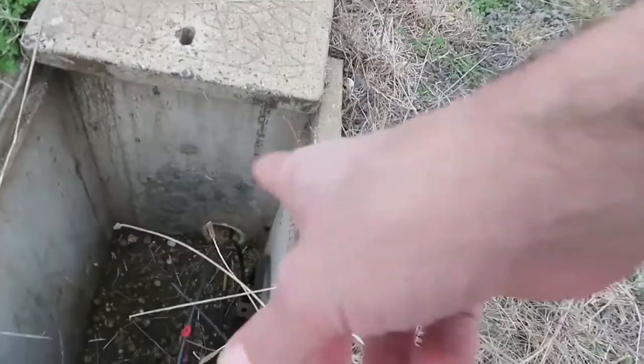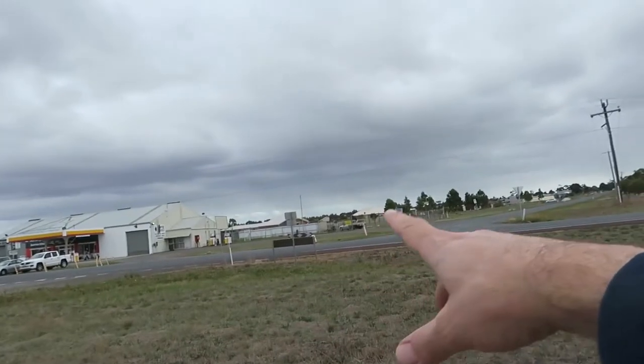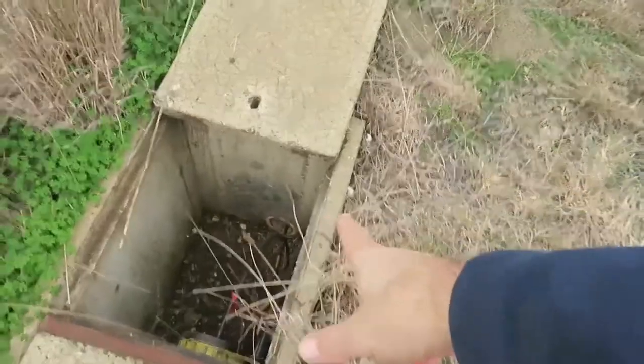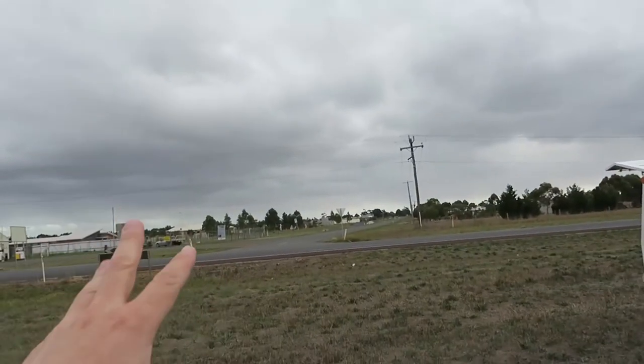The other thing to take note — see how you see it in pipe there? This optic fibre from here actually goes down, travels around, goes under the road and heads down that road. When communication cables go underneath roads, they'll generally put it in a pipe. So here they've got it in 100mm conduit — it stays in the 100mm conduit the whole way, goes around over to that marker in pipe. From that marker, it goes out of pipe again, direct buried, straight down that road.